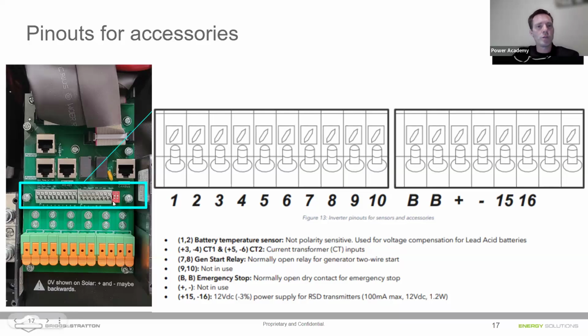This is where you'd put your two-wire start. If you have a generator relay, you'd be using pins 7 and 8. We'll talk about that in a bit. The emergency stop is a normally open circuit, and that's labeled B and B there. You'll need to have an emergency stop built in. Pins 15 and 16 are for the rapid shutdown connections, so the keep alive signal comes out of those.